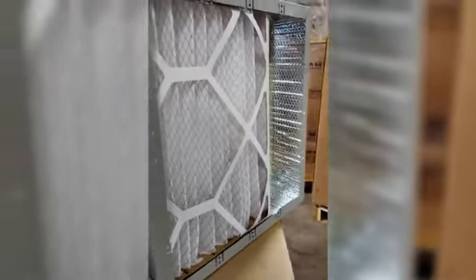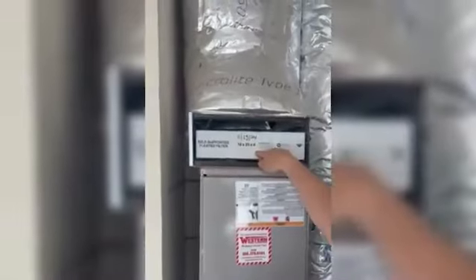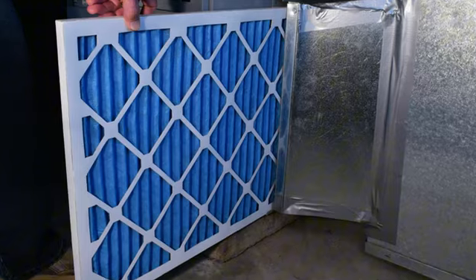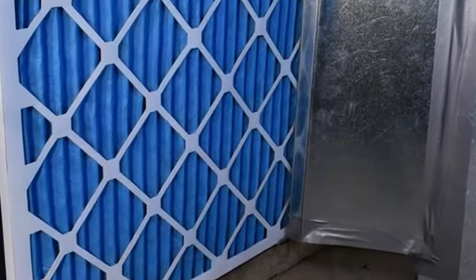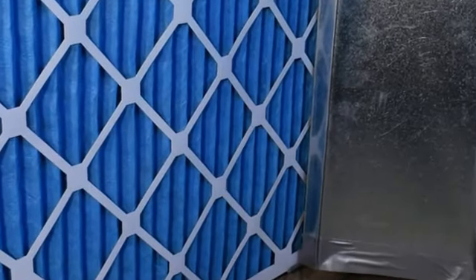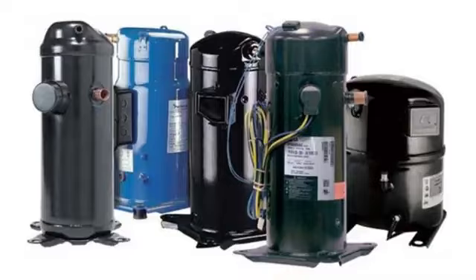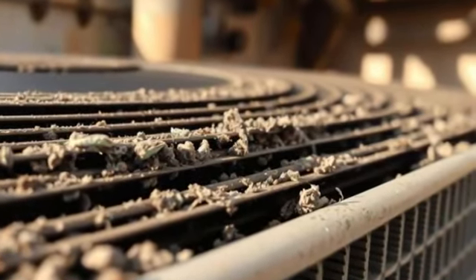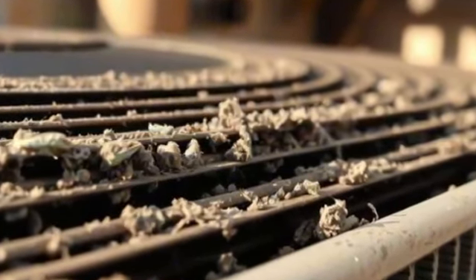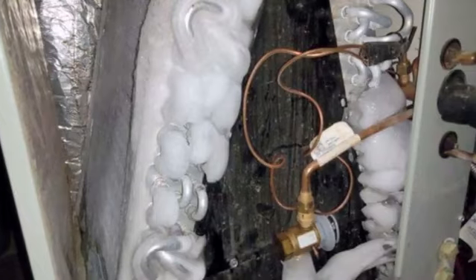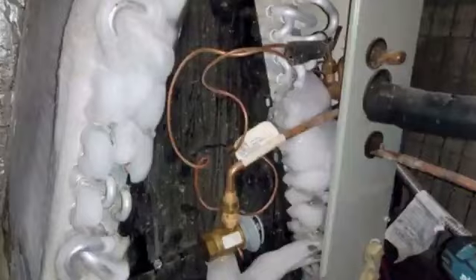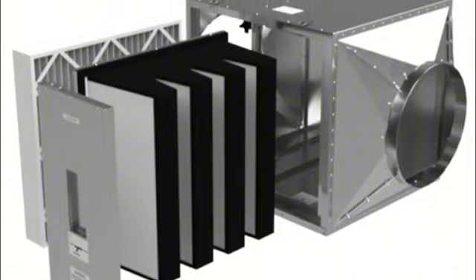Every HVAC system has a filter. Builders install the cheapest 1-inch fiberglass filter available, $1.50 each. These filters stop large debris. They do not stop dust. Dust accumulates on the evaporator coil. A coated coil cannot transfer heat. Airflow drops. The system runs longer to reach temperature. Longer run times accelerate wear on the blower motor, the compressor, the control board. A dirty coil also freezes because restricted airflow cannot remove condensation. Frozen coils mean water damage when they thaw. $800 to $2,000 in ceiling repairs. The fix costs $30. A 4-inch pleated media filter traps dust and lasts 6 to 12 months. Installing the filter box costs $200 to $350.